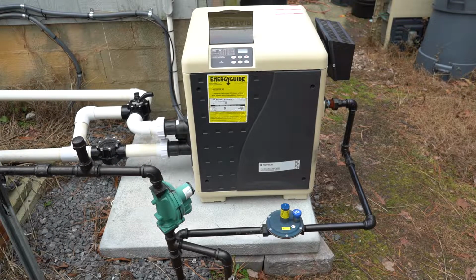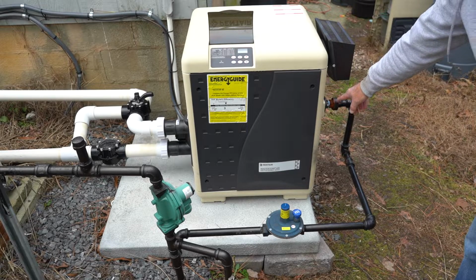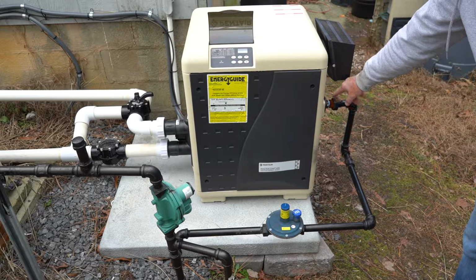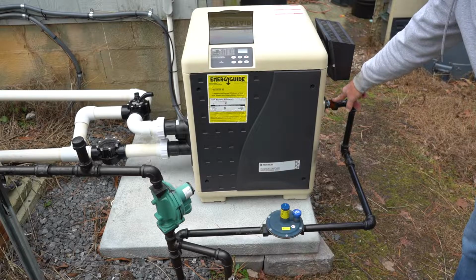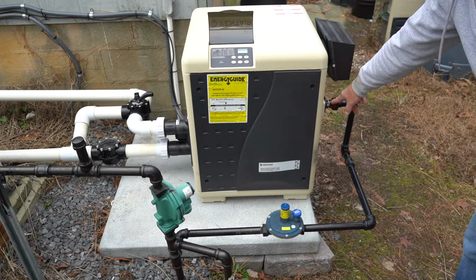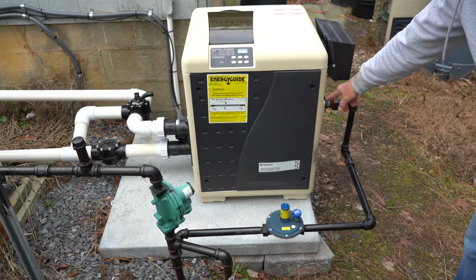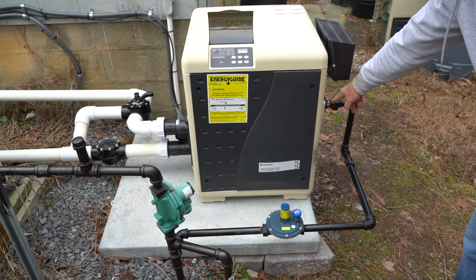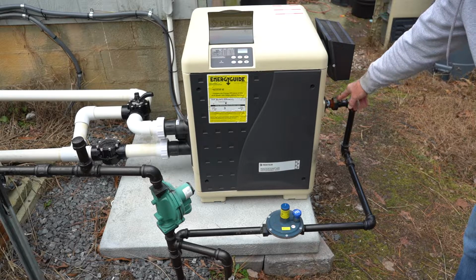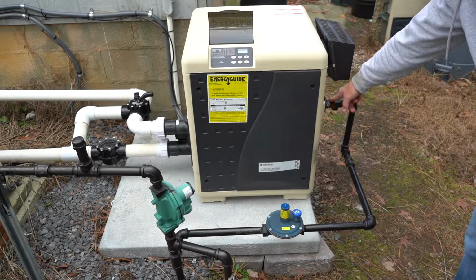Another very important thing on installing a heater: it is going to fail and you're going to have to take it out, replace it, or fix it. So it's very important that you put a union right on the end of the heater. You can use an 8-inch, 3/4 by 8-inch pipe that goes into the gas valve, and then put a union right here.